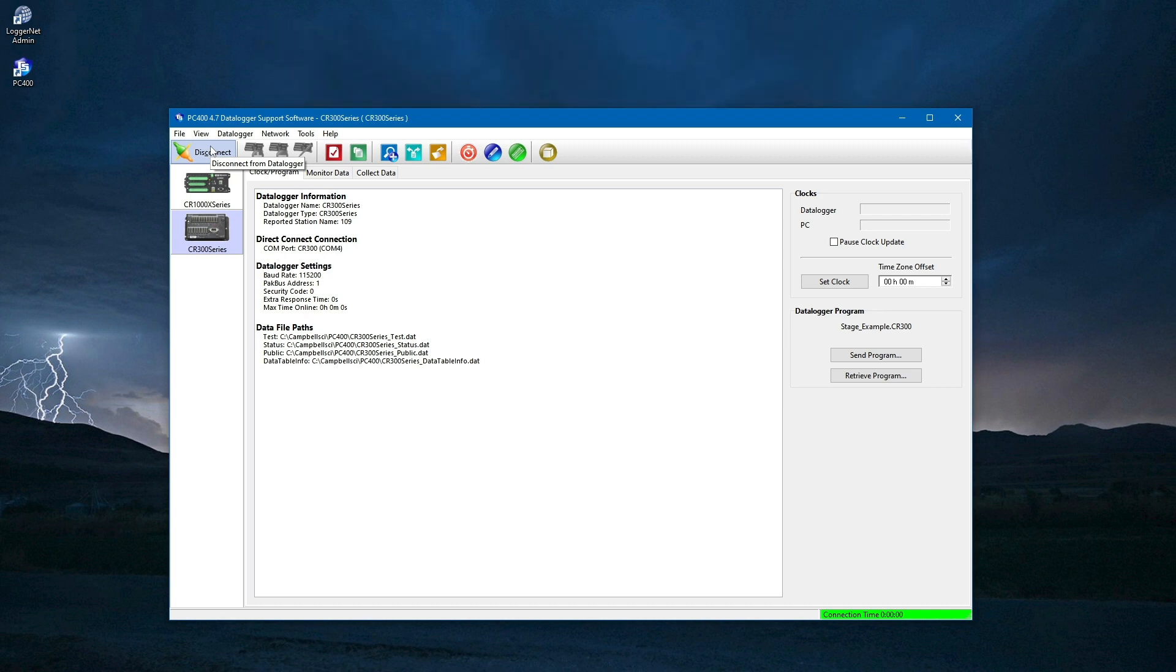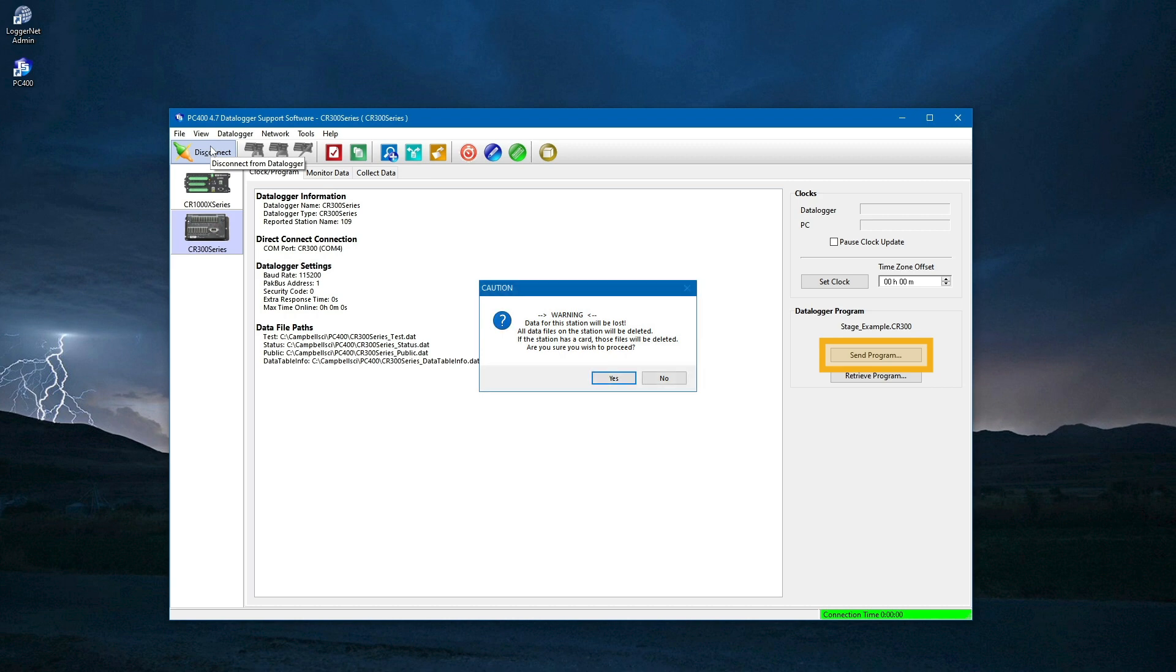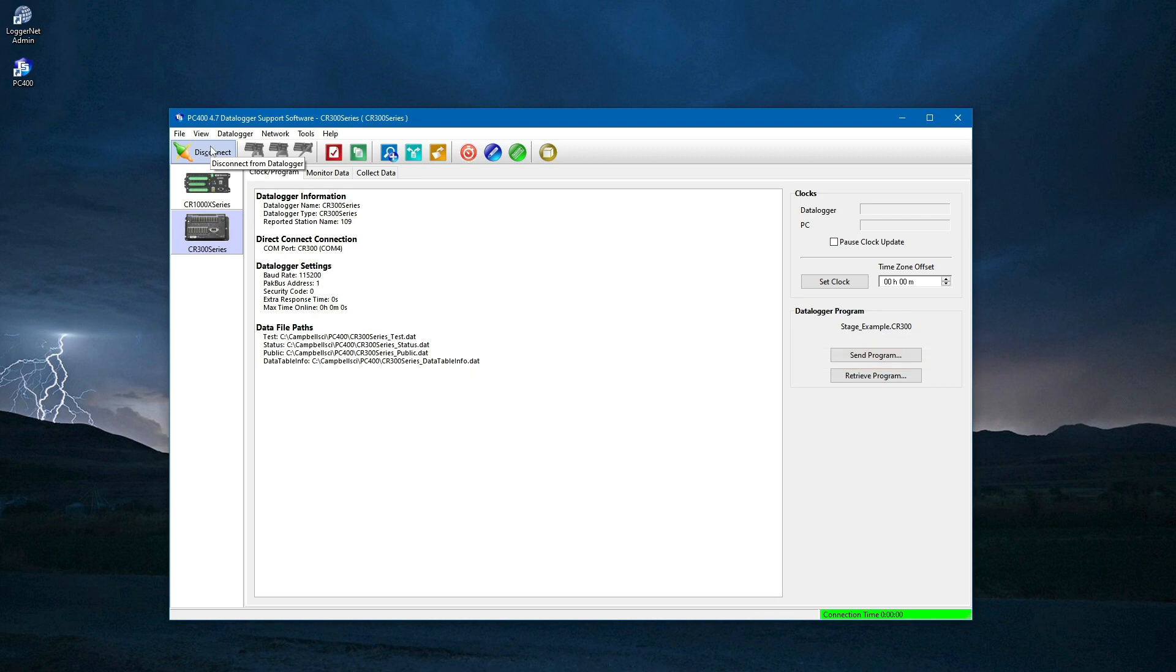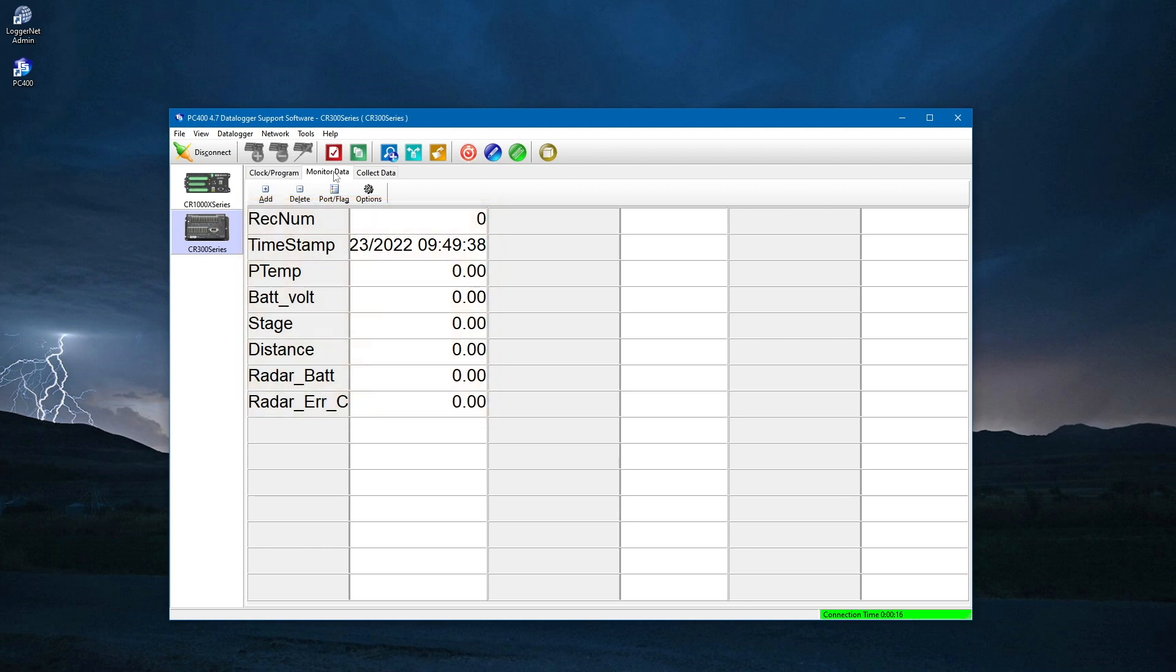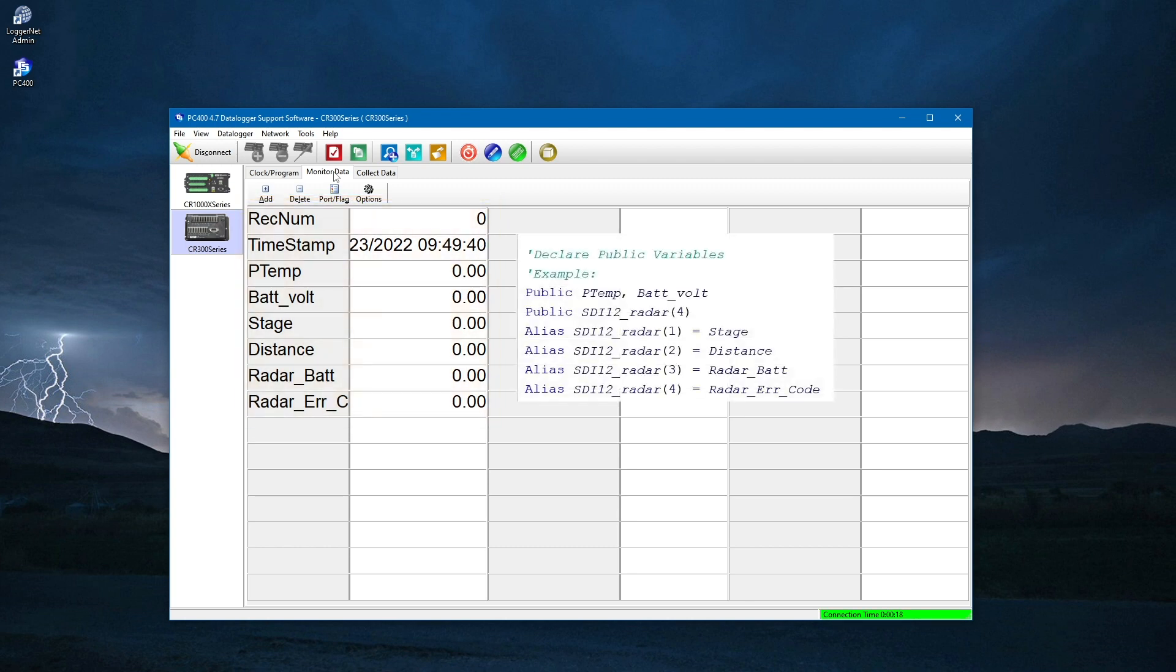An alternative way to send the program is to use the Send Program button on the Connect screen. This may be a safer way to send the program because in this case, I am warned to save any unsaved data. Once the program has compiled, I will go to the Monitor Data tab to view the public table. In the public table, I see the variables from the program which hold the data logger panel temperature and battery voltage, as well as stage, distance, radar battery, and any error code from the radar sensor. Notice that the order of these variables in the public table matches the order they are declared in the CRBasic program. This is why it is important to declare variables in a logical order based on function or grouped by sensor type, or whatever organization scheme helps me find the measurements I am looking for easily in the public table.